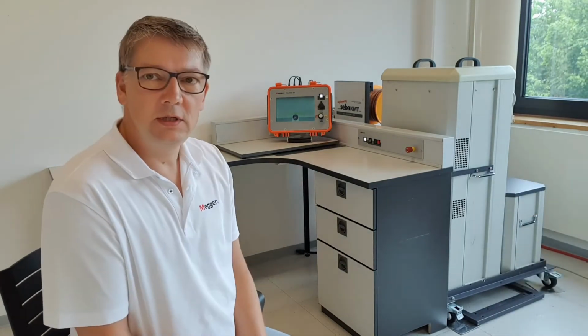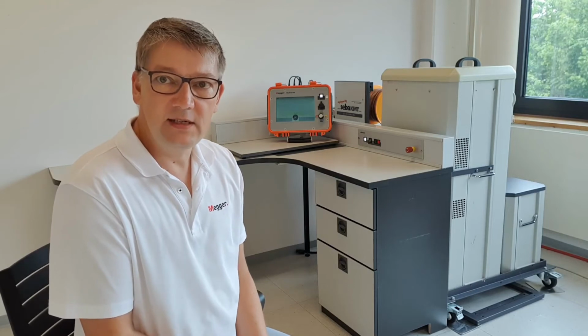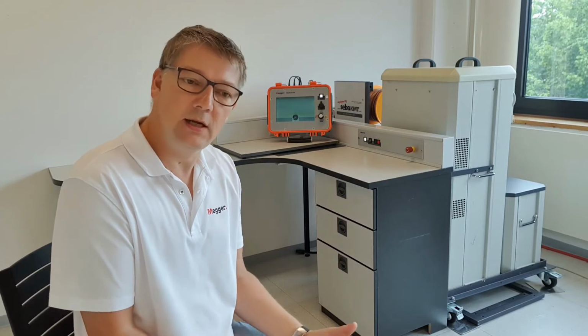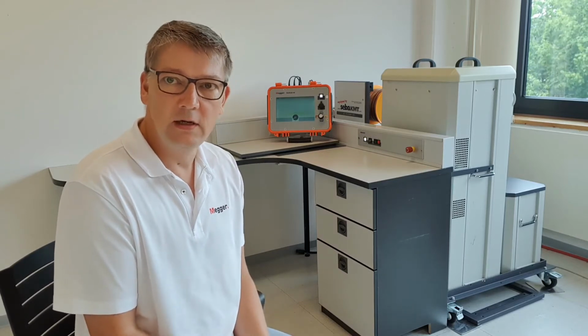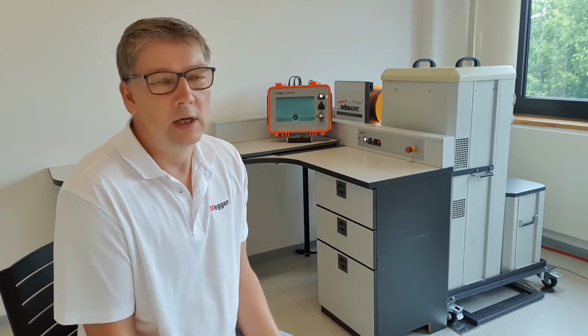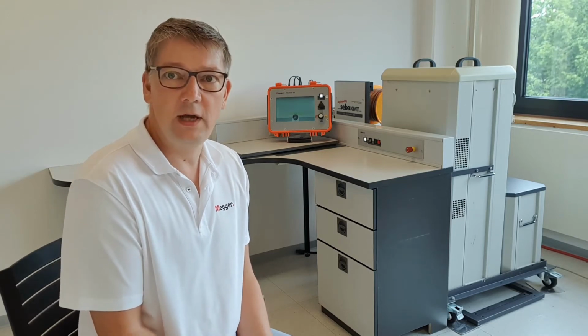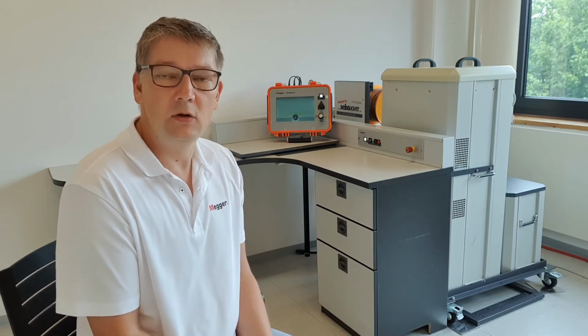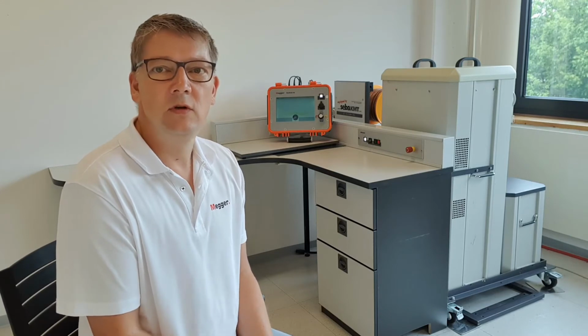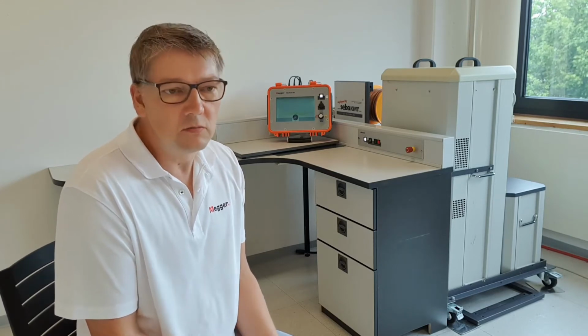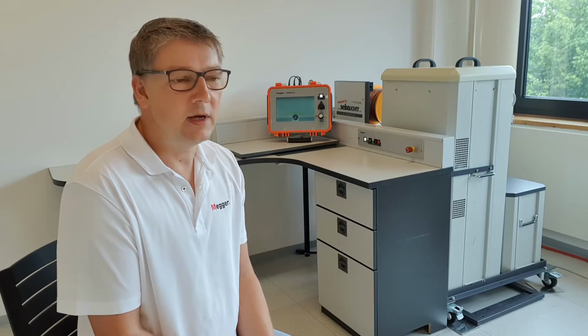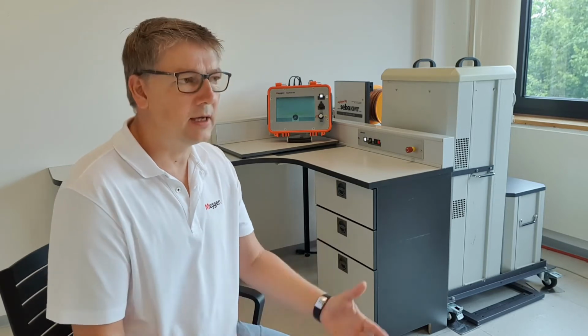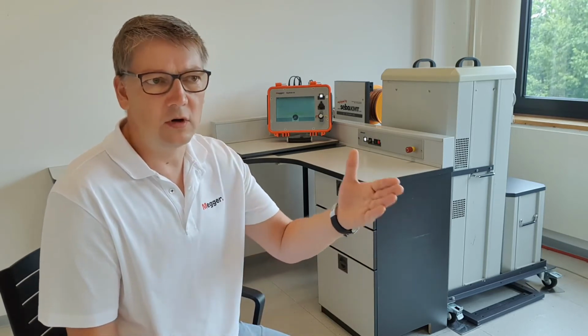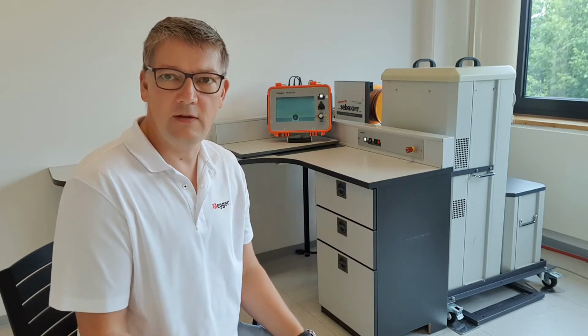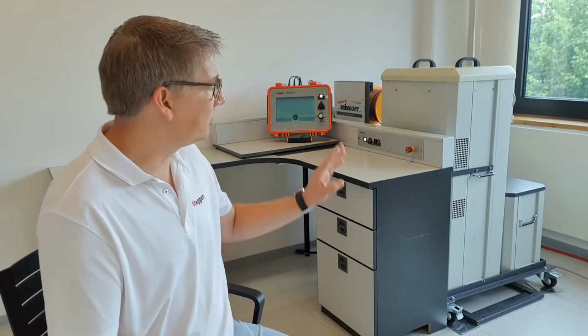The high voltage unit consists of a 40 kV DC tester and different surge ranges, starting with the lowest range, 2 kV, which is nice for low voltage cable fault locating, street lighting, and it goes up to 32 kV, which is then for medium voltage cables, maybe even high voltage cables. And in between you have different ranges like 2, 4, 8, 16, 32 kV. That's the high voltage unit.